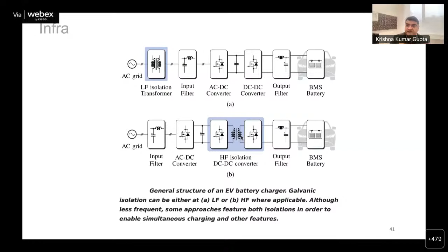Now, when you have high frequency isolation at the DC to DC conversion stage, the size of the core will be less, but the material used for the core is a bit brittle compared to the CRGO silicon steel used for low frequency transformers. So for high power applications, manufacturing these kinds of cores is very challenging because this material is brittle and you cannot easily shape it for the core. This is a big challenge.